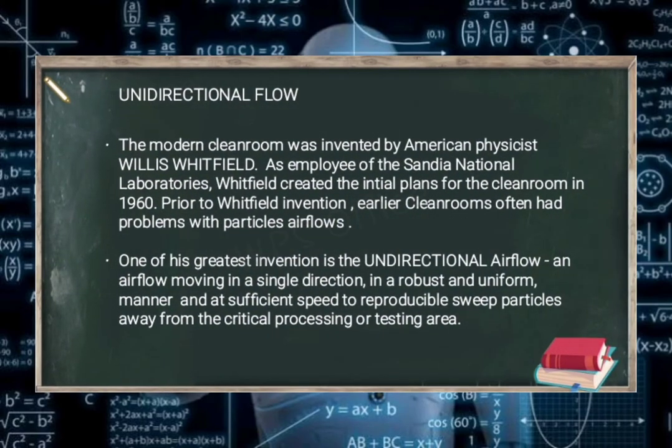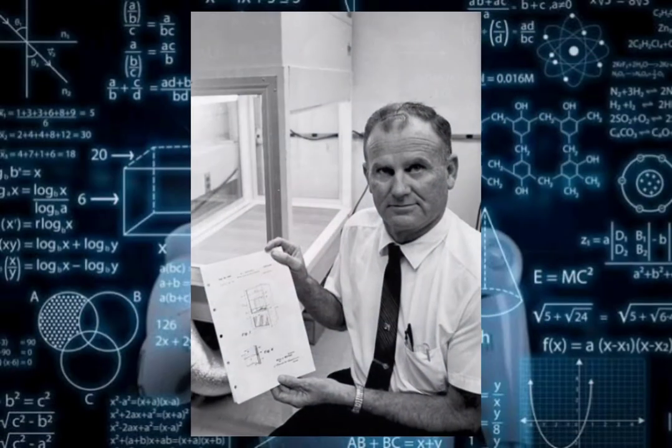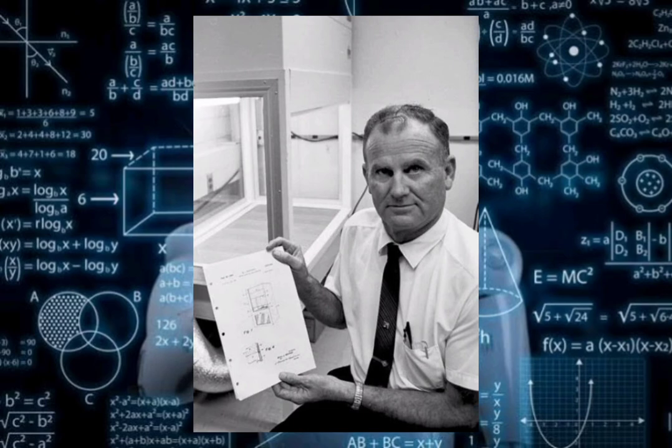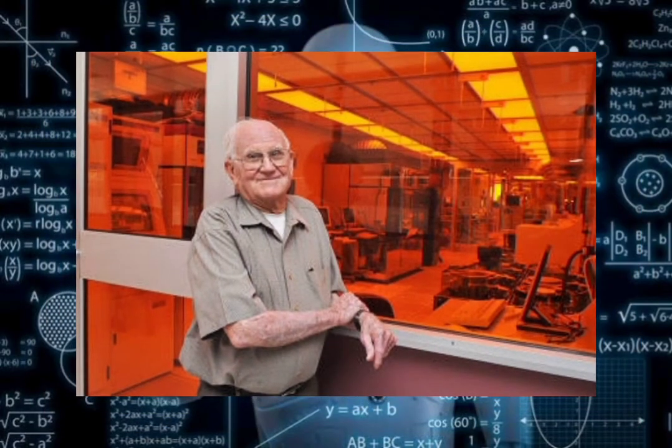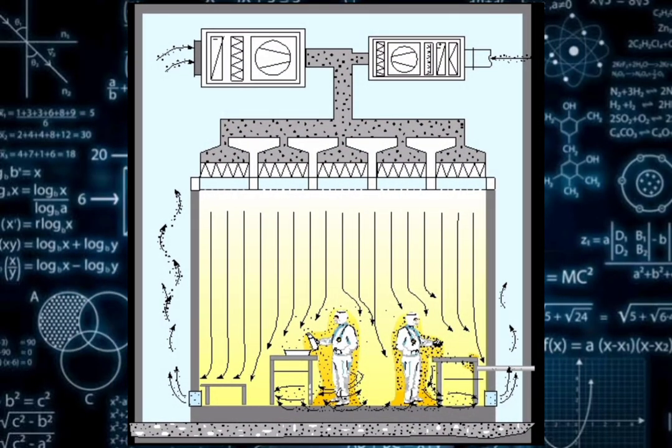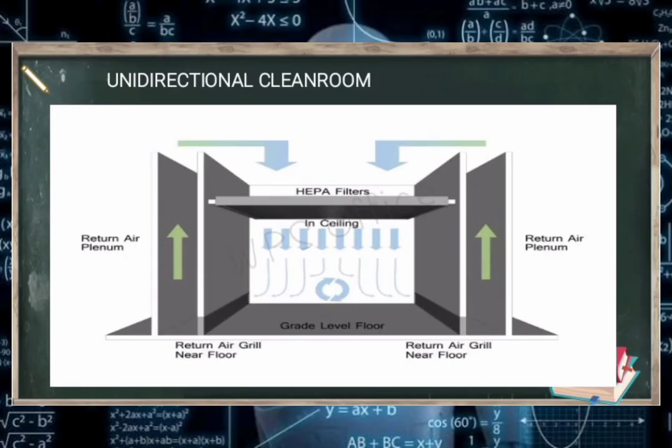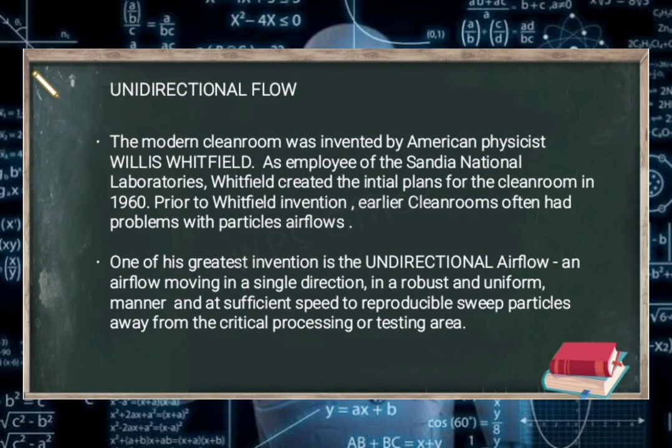The modern cleanroom was invented by American physicist Willis Whitfield, an employee of Sandia National Laboratories. Whitfield created the initial plans for the cleanroom in 1960. Prior to Whitfield's invention, earlier cleanrooms often had problems with particles and unpredictable airflows. One of his greatest inventions is unidirectional airflow—an airflow moving in a single direction in a robust and uniform manner and at sufficient speed to reproducibly sweep particles away from the critical processing or testing area.